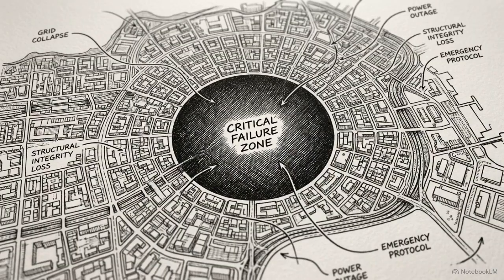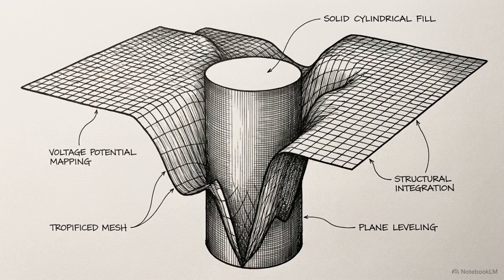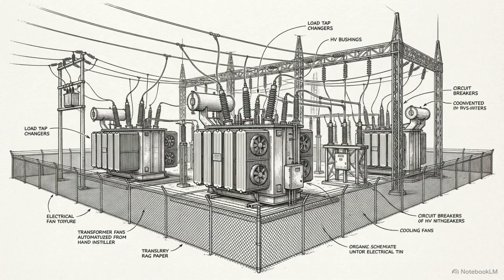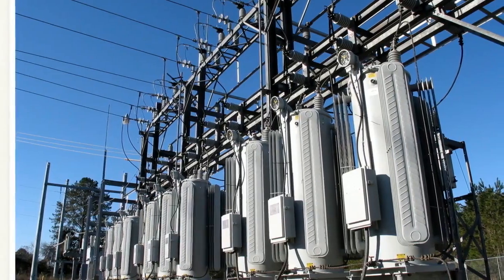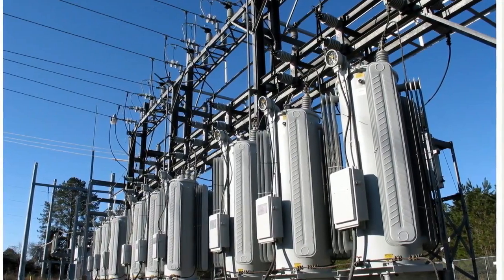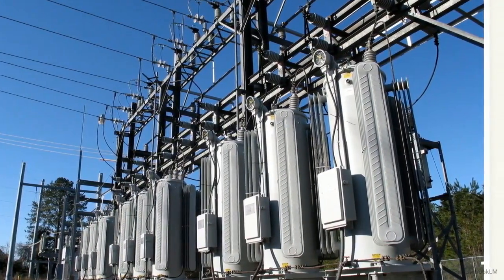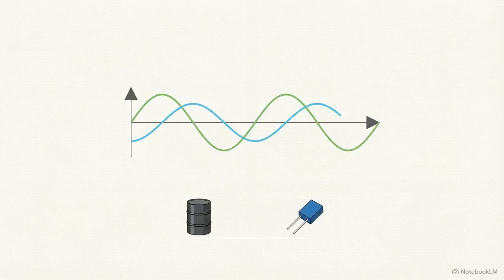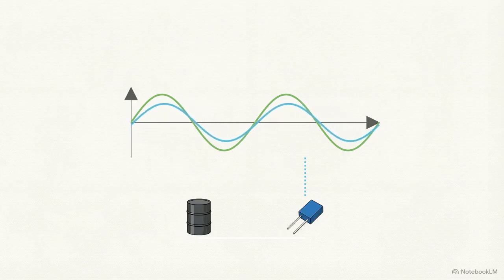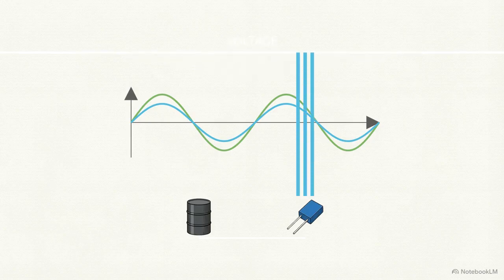To prevent a localized voltage collapse from ripping through the rest of the network, engineers have to fill those specific valleys with reactive power exactly where they occur. They solve this using a localized engineering technique called reactive power compensation. Instead of relying on a distant plant, they install specialized hardware right at the local substations. Devices like load tap-changing transformers mechanically adjust the voltage ratio while the system is actively running under heavy load. They also use shunt capacitors. These devices sit right next to the industrial motors and inject their own electric fields to perfectly cancel out the magnetic phase delays on the spot. They physically prop up the local voltage, so the main grid doesn't have to.